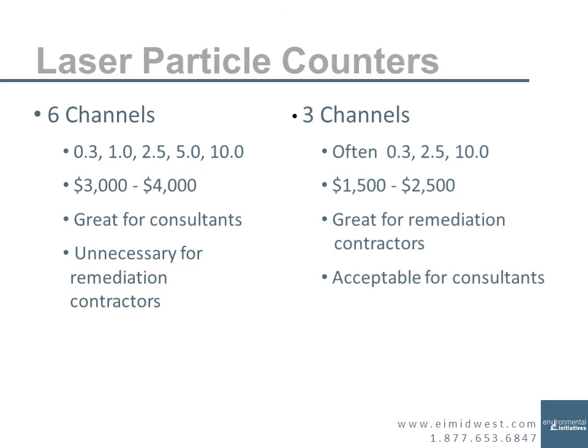Why the laser particle counters are nice is that you can compare different filters. When you start to take data from a lot of different equipment, you'll realize that some companies produce equipment that is really good at removing 0.3 micron particles. But then all of a sudden, because they made their filters in a certain way to catch that 0.3 micron, they've lost their ability to remove larger particles.